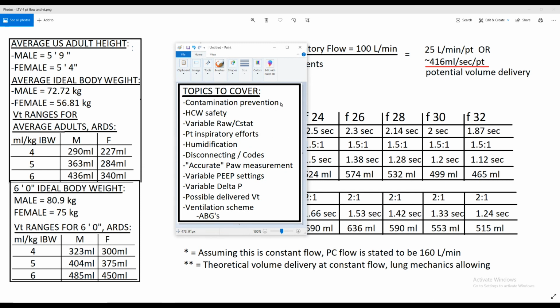Contamination prevention, we did that. That's the little check valve on the inspiratory limb and the bacterial viral filter on the inspiratory limb. Healthcare worker safety, we've got the bacterial viral filter on the expiratory side, as well as us going to clamp the inspiratory limb of any patient who has to be disconnected for whatever reason.